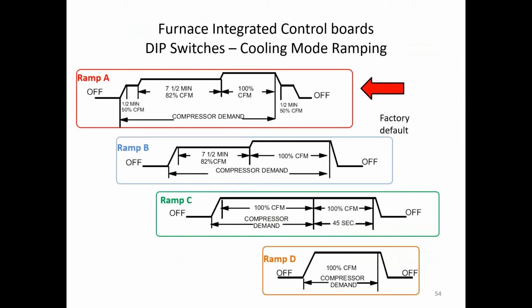Furnace air control comes from the factory as an A ramp. We have 4 different ramp profiles. I talked a little bit about that yesterday: the blower itself is not a normal cooling demand blower. In this scenario, on this furnace, the blower is going to come up and run at 50% air volume for about a half a minute. And then for the next 7.5 minutes, it's going to run at 82% volume. That's where we have it set at the factory by default.